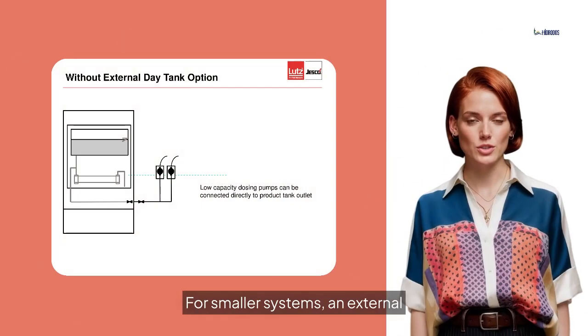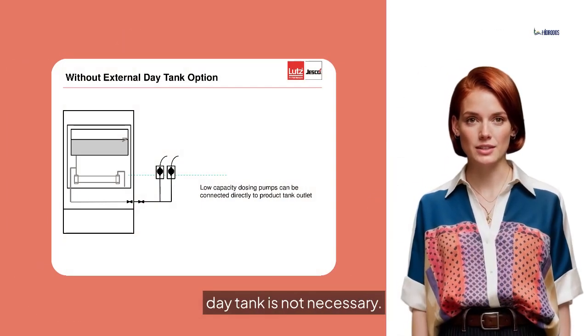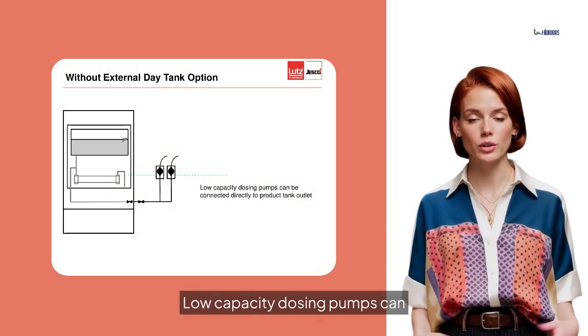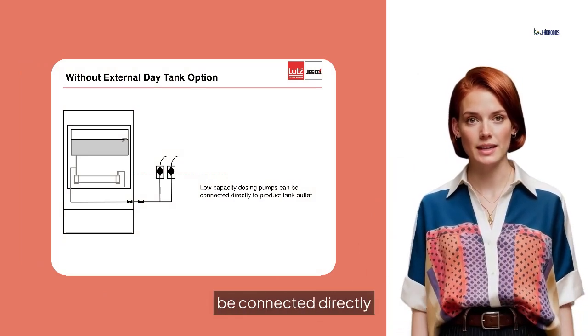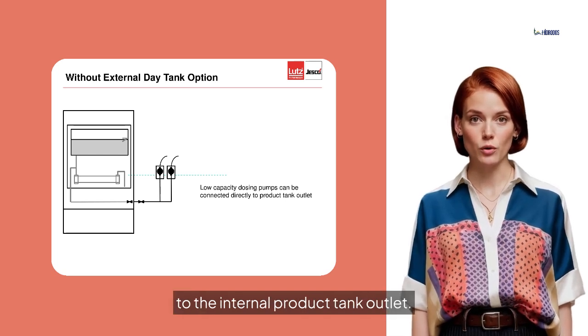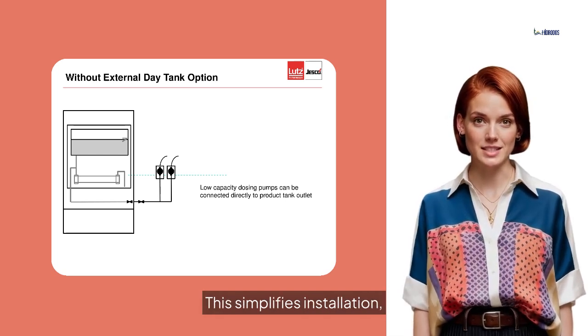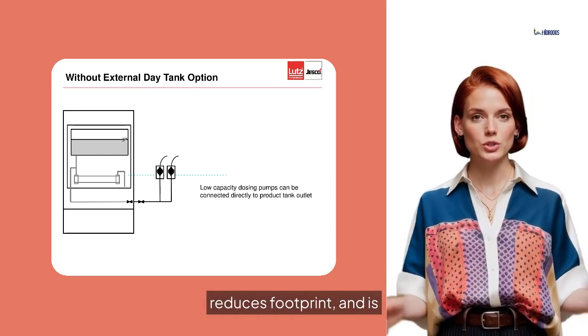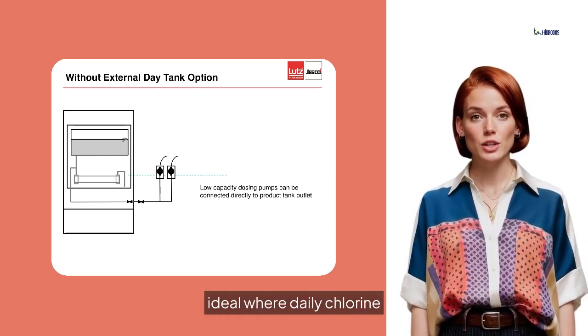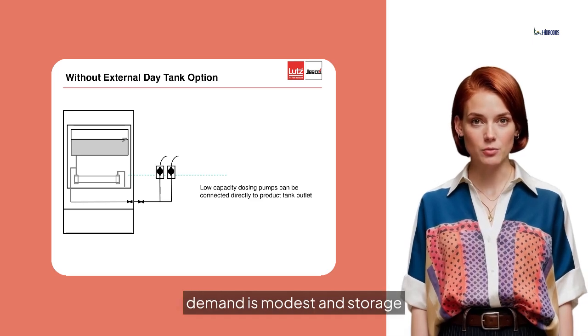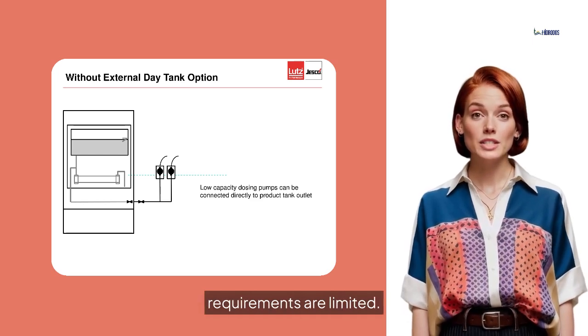For smaller systems, an external day tank is not necessary. Low-capacity dosing pumps can be connected directly to the internal product tank outlet. This simplifies installation, reduces footprint, and is ideal where daily chlorine demand is modest and storage requirements are limited.